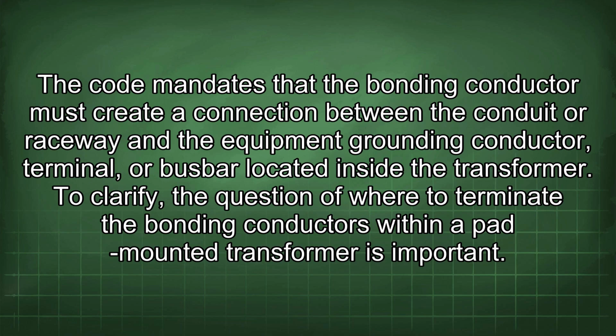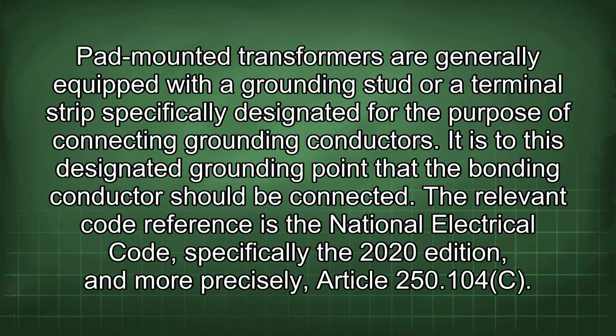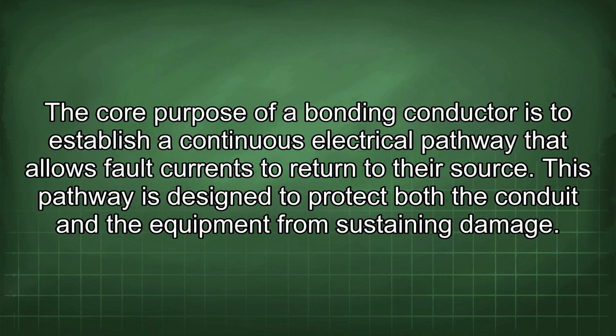To clarify, the question of where to terminate the bonding conductors within a pad-mounted transformer is important. Pad-mounted transformers are generally equipped with a grounding stud or a terminal strip specifically designated for the purpose of connecting grounding conductors. It is to this designated grounding point that the bonding conductor should be connected. The relevant code references the National Electrical Code, specifically the 2020 edition, and more precisely Article 250.104(C). The core purpose of a bonding conductor is to establish a continuous electrical pathway that allows fault currents to return to their source. This pathway is designed to protect both the conduit and the equipment from sustaining damage.